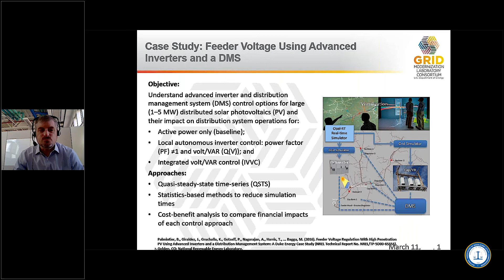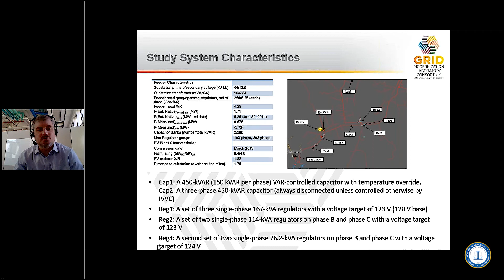Just to give you a rough idea of the system we're looking at, it's a medium voltage system, pretty typical. It has a number of voltage regulators and capacitors on it. These are effectively the tools that the utility had before the PV system was installed in order to control the voltage on the distribution system, whether doing CVR or not. There's a rough diagram in the upper right, but this is probably something that doesn't look too far off what you see in the southeast quite often.